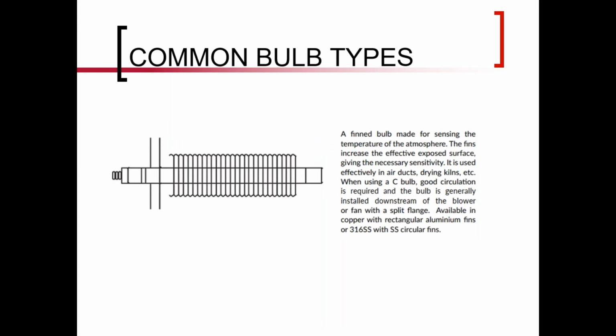I do see a fin bulb pretty frequently. This is more if you're doing temperature control of like a warehouse, where the fins will help pick up. They'll be a little bit more sensitive than just a regular bulb, and this will often be in the ductwork. So if you're heating a warehouse, this will be up at the top in the duct, if you've got a natural gas heater that is providing warm air through the duct. So I see that a lot, or sometimes even in larger maintenance shops where they've got this, and it just senses the temperature of the air as it goes through the ducts.